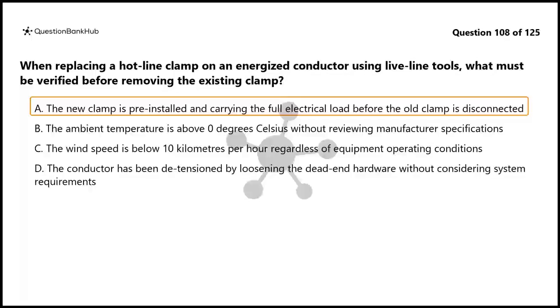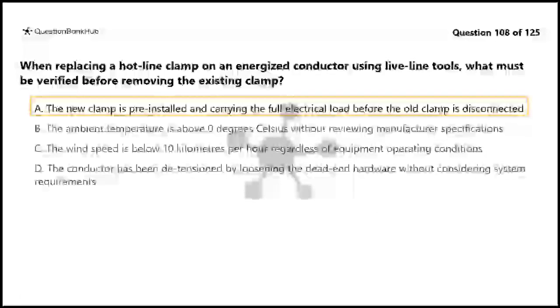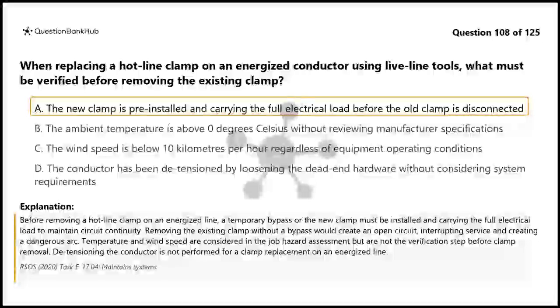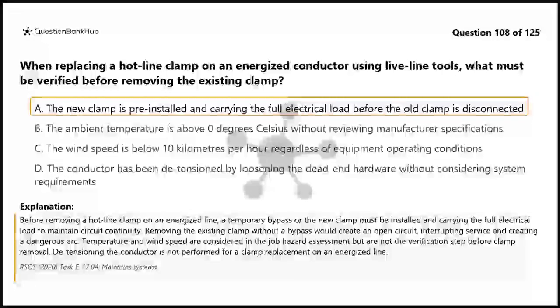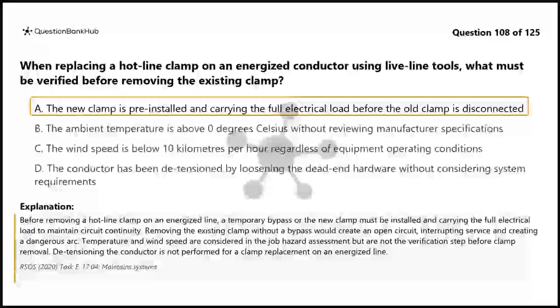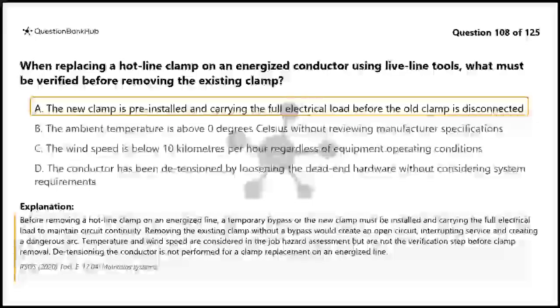The correct answer is A. Before removing a hot line clamp on an energized line, a temporary bypass or the new clamp must be installed and carrying the full electrical load to maintain circuit continuity. Removing the existing clamp without a bypass would create an open circuit, interrupting service and creating a dangerous arc. Temperature and wind speed are considered in the job hazard assessment but are not the verification step before clamp removal. Detensioning the conductor is not performed for a clamp replacement on an energized line.